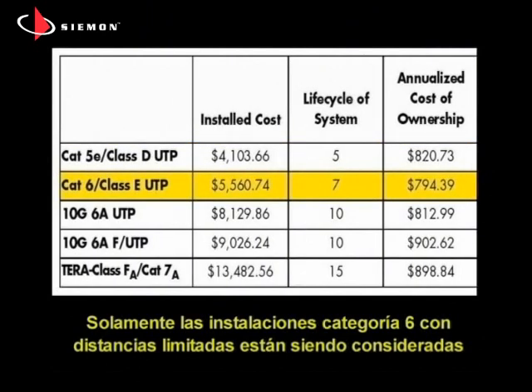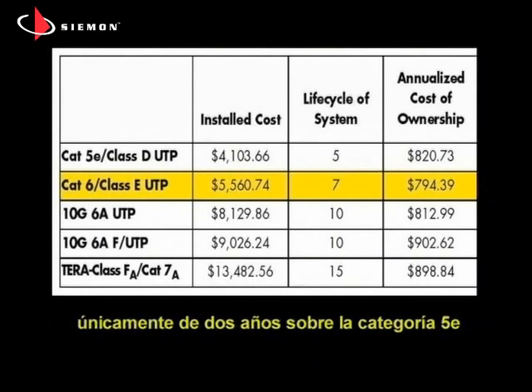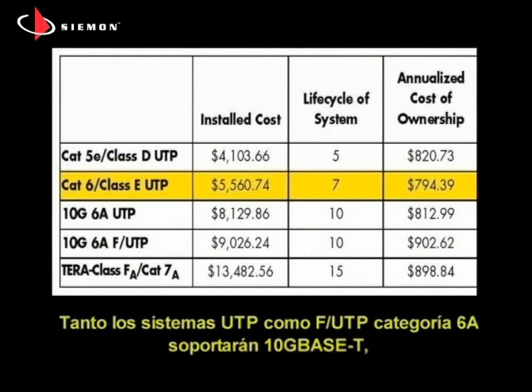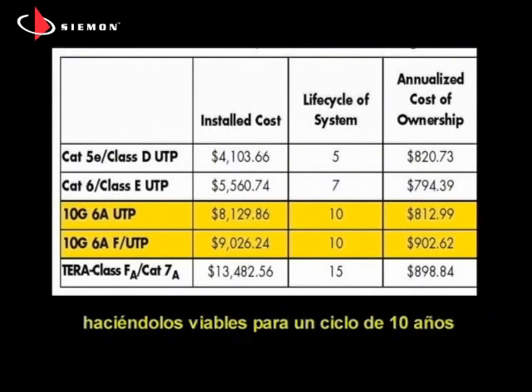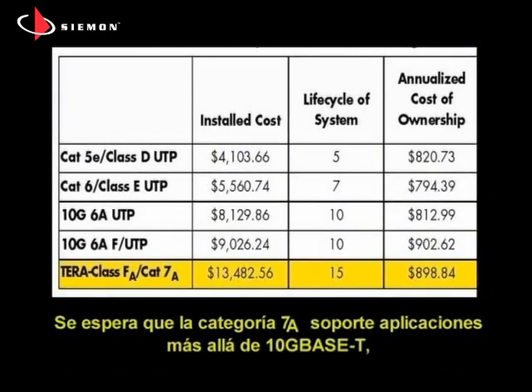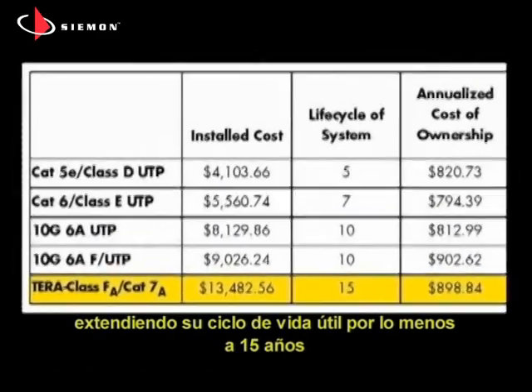Only legacy Category 6 installations are being considered for 10 gigabit applications over a limited distance, giving Category 6 only a 2 year advantage over Category 5E. Both UTP and F/UTP Category 6A systems will support 10G Base-T, making them viable for a full 10 year life cycle. Category 7A is expected to support applications beyond 10 gigabit Ethernet, extending its useful life cycle to at least 15 years.